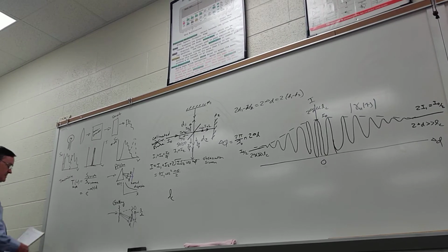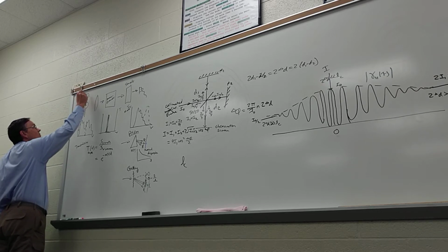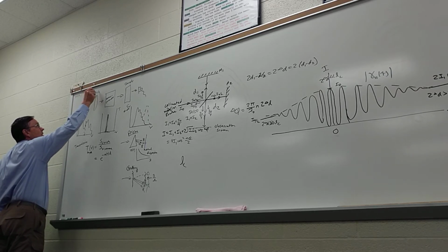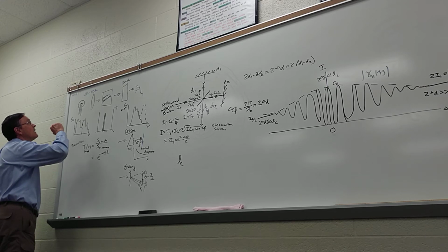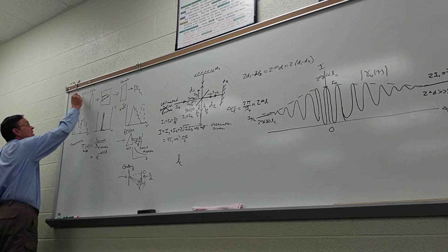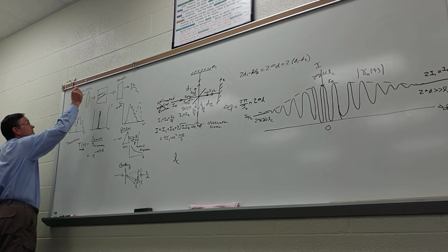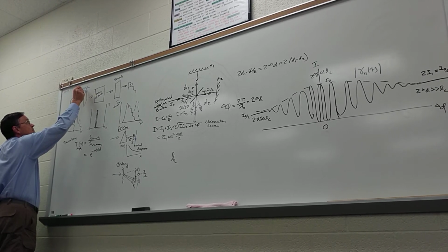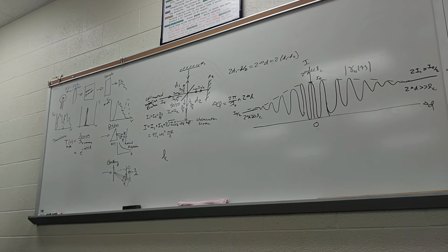So if you have a sample and you're trying to make this measurement, say from the UV to the near IR, this is the way you want to do it. Works great. A typical spectrometer will often have a range of 190 nanometers on the short wavelength side to maybe 1900 nanometers on the long wavelength side. That's pretty typical for a spectrometer.